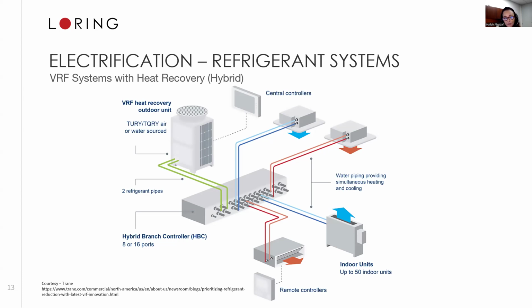The other type of VRF system, or variable refrigerant flow system, is a sort of hybrid solution that provides refrigeration through a refrigerant-based system between the outdoor unit and what we call a controller or collector box. And then it uses traditional water-based systems to all of your indoor units. This is something that you could use, for example, if the owner does not want to invest in wholesale modifications and they already have a water-based system. But also, we at times have used this system where you have limitations on where you're using refrigerants within the building.